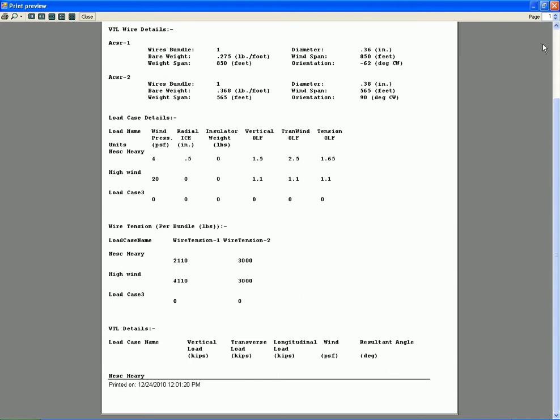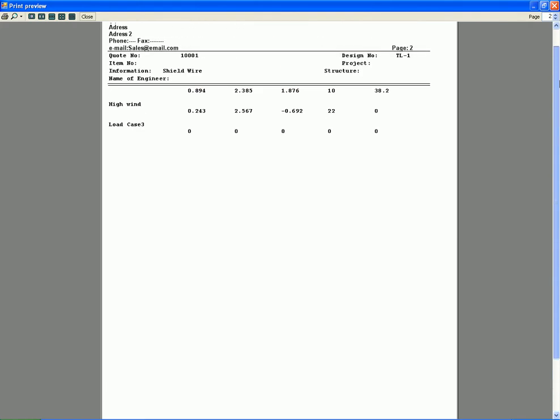And then come to the second page of report. This is your final loads: 0.894 for the NESC heavy, 2.385 kips transverse load for the NESC heavy load case, 1.876 kips for the longitudinal load, and wind PSF 10, and the angle is 38.2. Thank you very much - it will save the time of engineer.